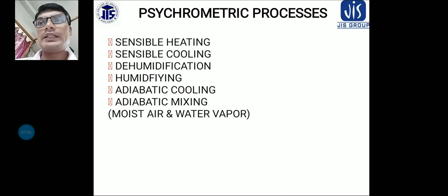Okay. So this WS is the specific humidity of air when air is fully saturated. Okay, now let us discuss sensible heating. What do you mean by sensible heating? Sensible heating can be described as when the air passes over a dry surface which is at a temperature greater than its dry bulb temperature, it undergoes sensible heating. Okay, so this heating can be achieved by passing the air over a heating coil, like an electric resistance heating coil or steam coil.